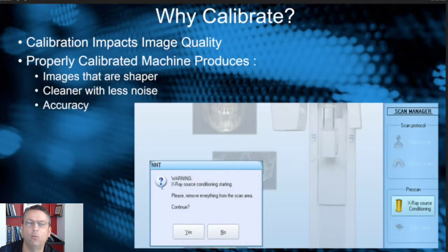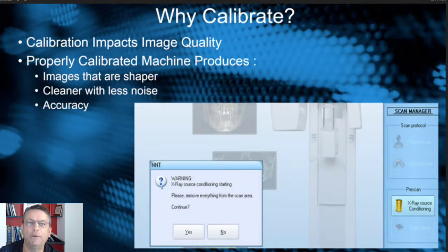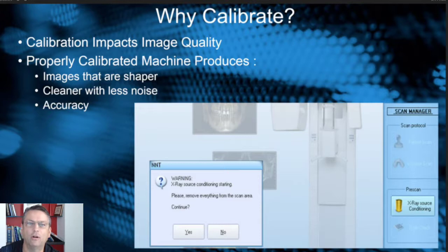Why calibrate? I asked this to some of the engineers that build cone beam CTs to understand it better. They tell me calibration directly impacts image quality, and when a properly calibrated machine is aligned it produces images that are sharper, cleaner, with less noise and more accurate. You may do a routine oil change in your car to keep things lubed up correctly — calibration is similar, where you want to keep things tuned up to the best quality.